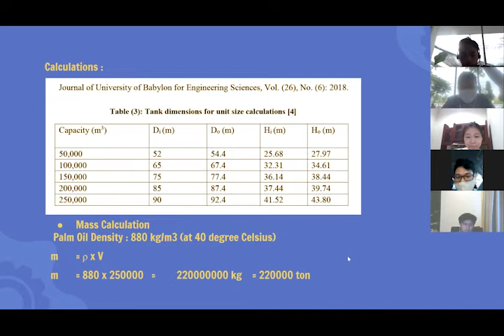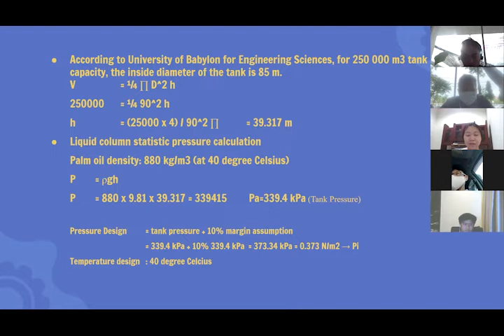And according to the University of Babylon for Engineering Science, we get the data for the diameter that is suitable for a 250,000 cubic meter tank capacity, and the diameter is around 90 meters, and we got the height is 39.317 meters. Then we calculate the pressure, and we got the pressure is around 339.4 kilopascals, and for the design pressure we add a 10% margin assumption, so we got around 0.373 N per square millimeter, and for the design temperature we use 40 degrees Celsius as the maximum operating temperature assumption.